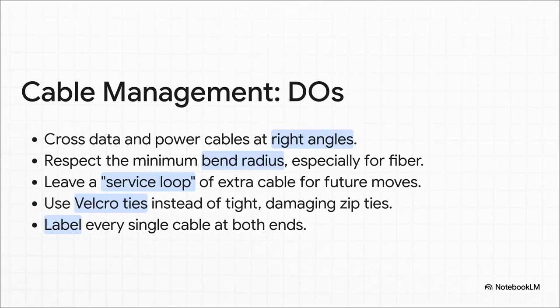Always cross your data and power cables at a 90-degree angle to avoid interference. Respect the bend radius. If you put a sharp kink in a fiber cable, you've just created a very expensive piece of trash. Always leave a service loop, just a little bit of slack for the future. Use soft Velcro ties, not plastic zip ties that can crush the cable. And, for the love of all that is holy, label both ends of every cable.